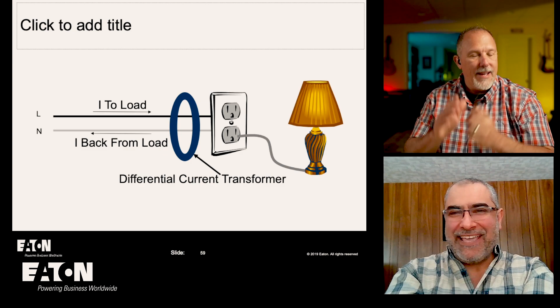And how a GFCI functions is it looks at the difference of current. Whatever goes out on that hot wire has to come back on the neutral. If this is three-phase, all three hot wires, and if there's a neutral involved, you would put all of those in the donut, but you don't put the equipment grounding conductor in the donut.